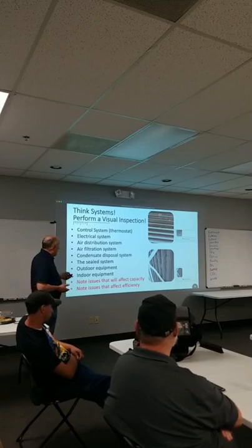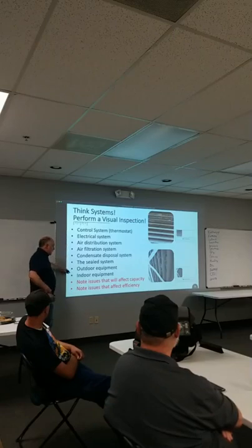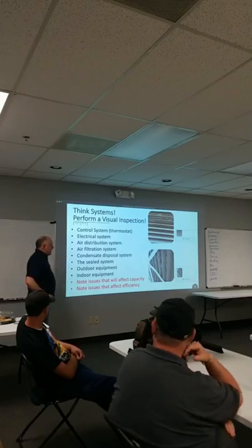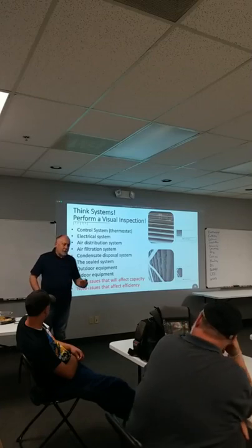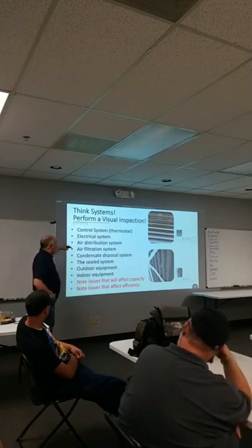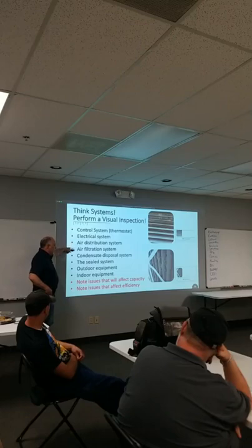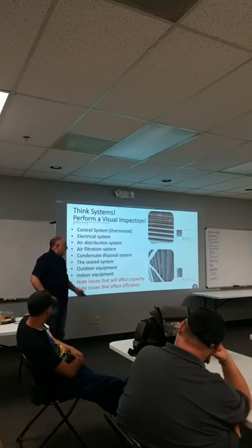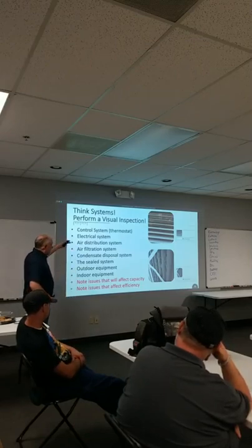One of the things I always have people do when I'm teaching this is think about all these as subsystems. Everybody gets fixated on the equipment. They try to fix all the problems with the equipment. Well, you have a control system, which is your thermostat. You have an electrical system, an air distribution system, an air filtration system, a condensate disposal system, your sealed system, your outdoor equipment, and your indoor equipment. And all these subsystems are impacting the operation of the equipment, right?